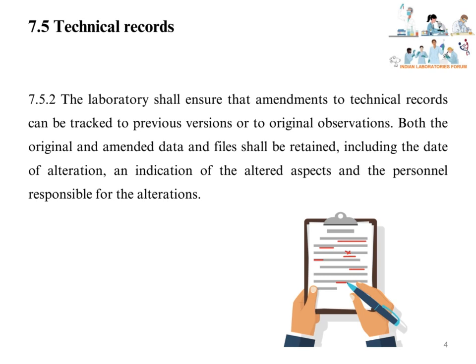The laboratory has to maintain the traceability of amendments to technical records back to the original observation. Both the original and amended data and files shall be retained, including the date of alteration, indication of the altered aspects, and the personnel responsible for the alterations. All amended records with original observations should be retained for legal and knowledge purposes.